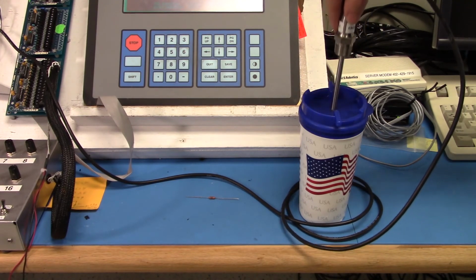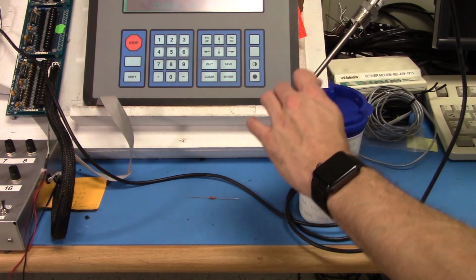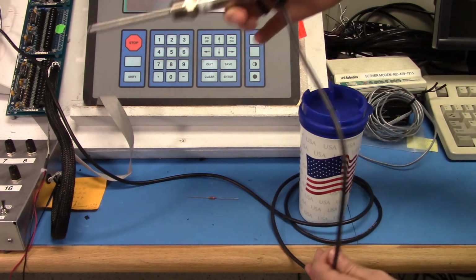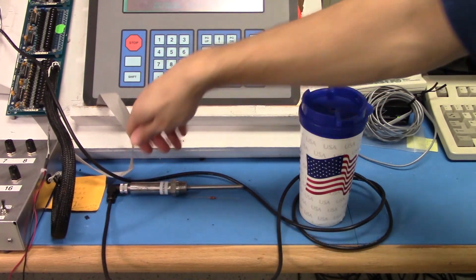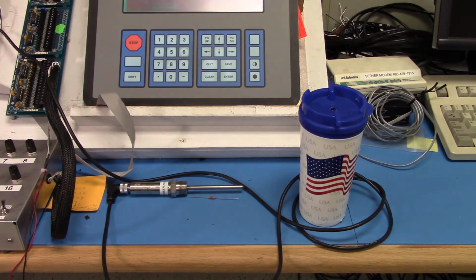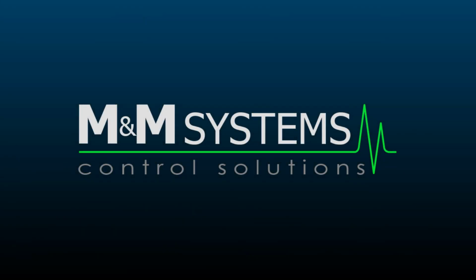That's it. Your sensor is now calibrated to 32 degrees. It can be removed, cleaned, and put back into service. It's worth noting that this calibration is for sensors that are working properly and within their spec. In most cases of sensor failure, there's either no reading or the sensor reads a static number of its minimum or maximum range. In this case, calibrating the sensor will not make any difference.